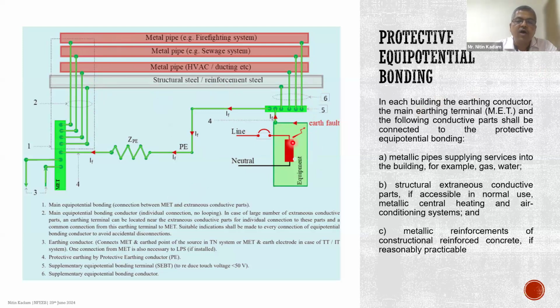And in case of fault, how does this help? In case of fault, you have multiple paths for the fault current to flow, thereby bringing down the fault loop impedance value, and therefore this helps the automatic disconnection of power supply. This kind of bonding also brings the potential of all the connected members to one value, at which this MET is connected, so basically ground potential. Since all the equipment and conductive parts are at one potential, when a person touches an installation's conductive part in case of fault and the other extraneous conducting surface, the shock hazard would not exist. So there are two benefits. One is about the shock hazard, and the other is about giving a low impedance value, which helps to disconnect the power supply in case of earth faults.